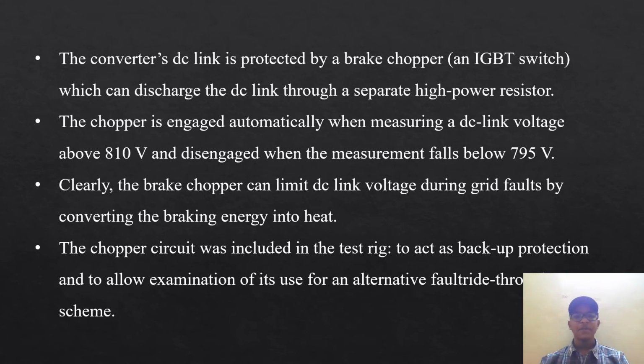The DC link is protected by the brake chopper, which discharges the DC link through a separate high power resistor. Clearly, the brake chopper can limit the DC link voltage during grid faults by converting the braking energy into heat.